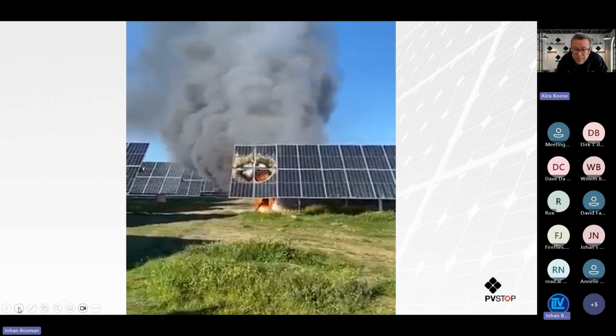Left unattended, this will burn out, but it'd be like a Chinese firecracker. Once you set fire, or the panels themselves start burning, that will just continuously burn from left to right. So there's some challenges around how this can be approached. It's an electrical origin source, water. Excessive volumes of water can be effective, but that water will dry out, evaporate, and then the problem could reignite. So secondary reignition is a big challenge around this. This is a challenging picture in terms of how do you even start to approach an incident like this.